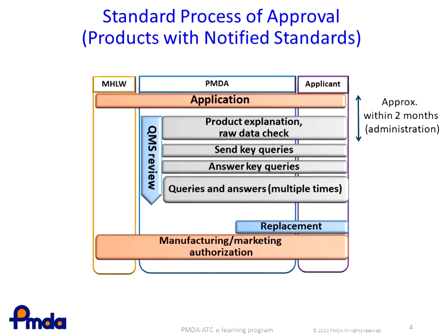This is the target timeline of the approval process for ordinary products, for which expert discussion is not required. The administrative process of document review and raw data analysis takes approximately two months after receiving an application. After the review, some key inquiries and answers are exchanged between the applicant and PMDA, and iteration of inquiries and answers for further clarification continues for about four months.